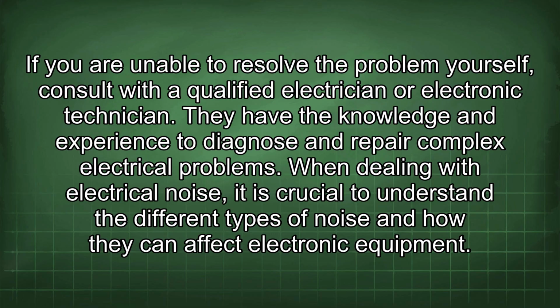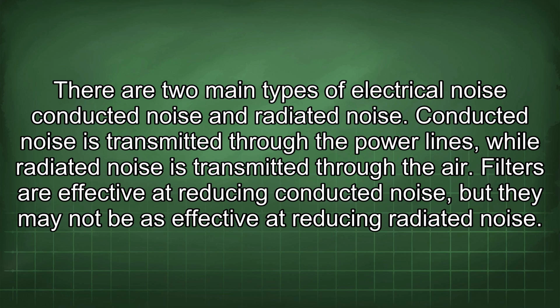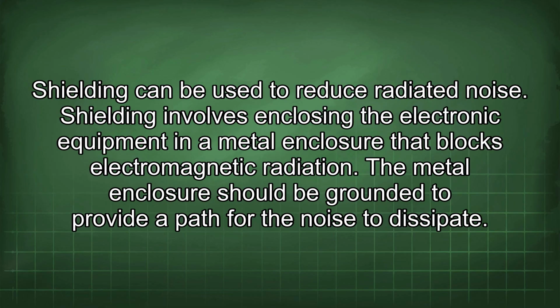When dealing with electrical noise, it is crucial to understand the different types of noise and how they can affect electronic equipment. There are two main types of electrical noise: conducted noise and radiated noise. Conducted noise is transmitted through the power lines, while radiated noise is transmitted through the air. Filters are effective at reducing conducted noise, but they may not be as effective at reducing radiated noise. Shielding can be used to reduce radiated noise. Shielding involves enclosing the electronic equipment in a metal enclosure that blocks electromagnetic radiation. The metal enclosure should be grounded to provide a path for the noise to dissipate.